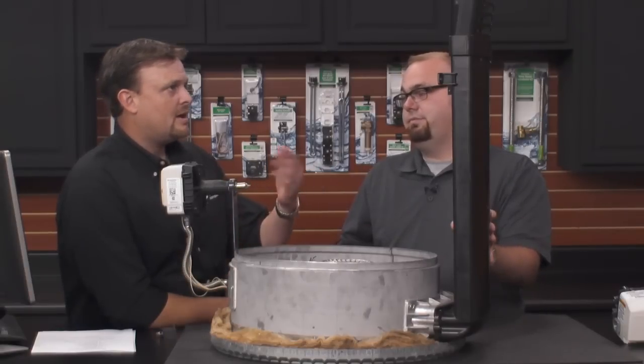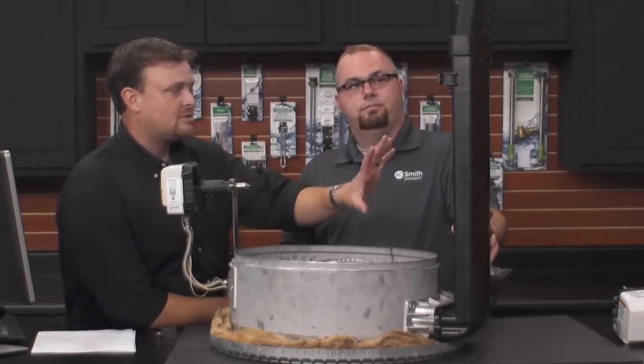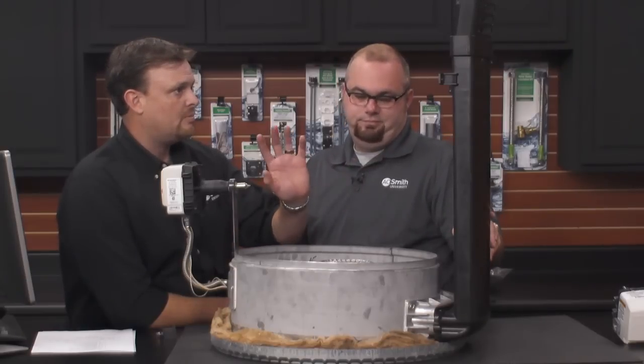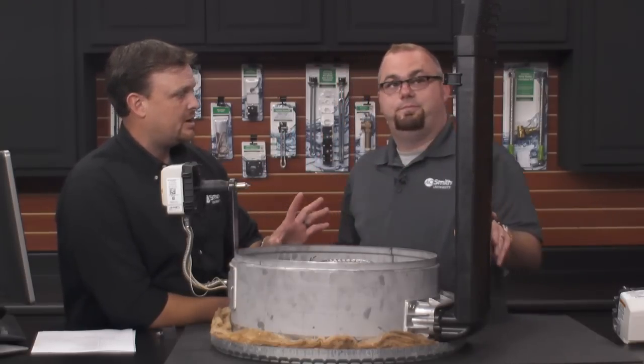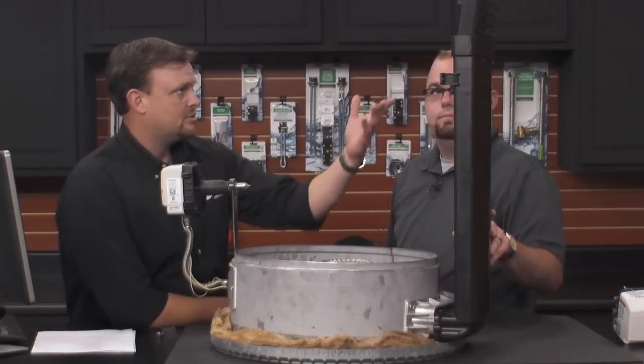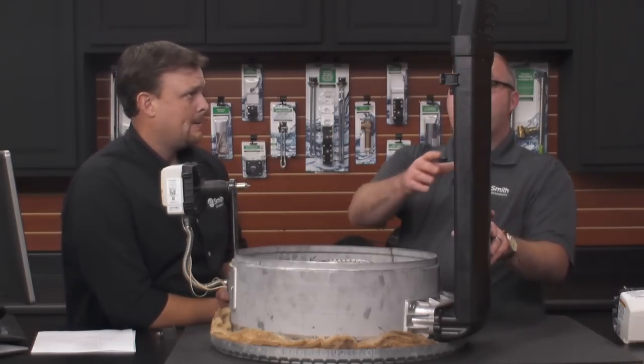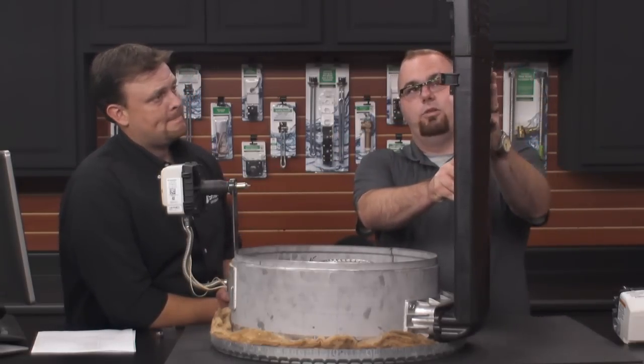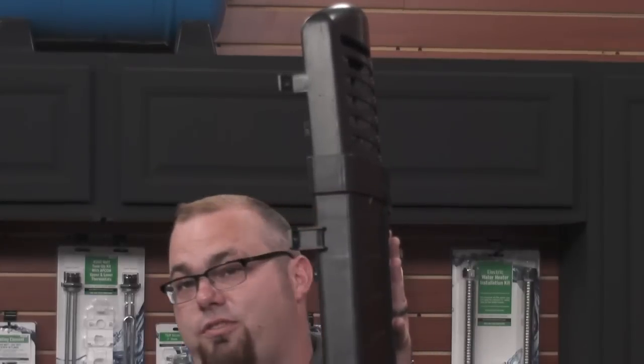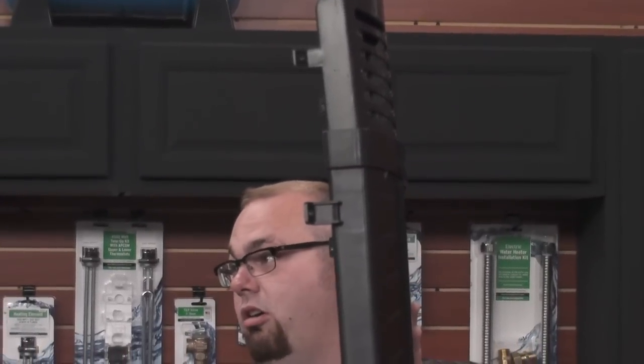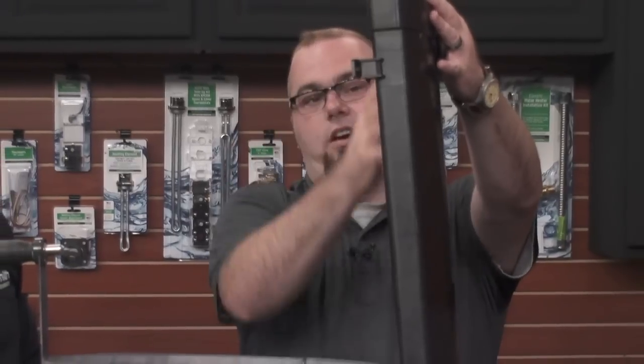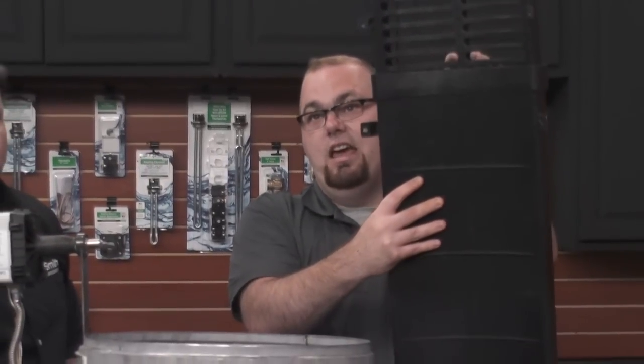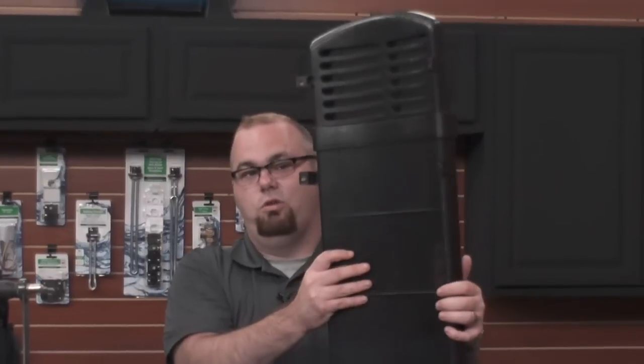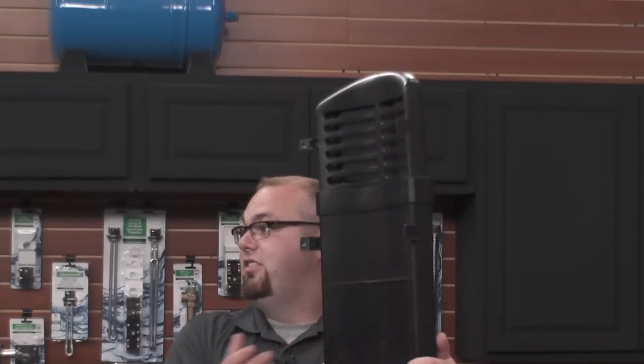Now, since it's on the back of the water heater, if I put it up against the wall, are we going to cut these louvers off? Is that going to be a problem? Well, the thing is this vent assembly or snorkel assembly is curved. So yes, if you fit it into an unfinished wall, you do have the potential of blocking off these back intake vents right here. But the good thing about it is it's also open right here on the other side. I can pull it off where you can see. It's open on both sides. It's contoured to where it fits up against the heater. And so it's still going to get air.